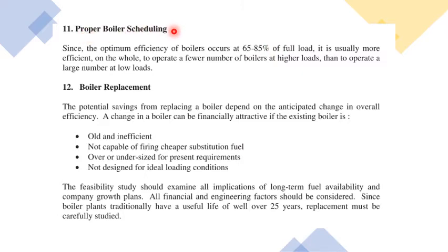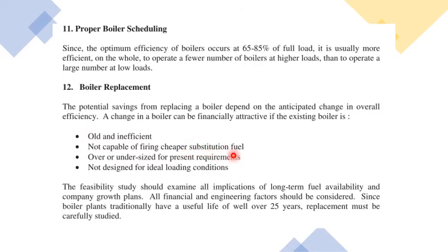The twelfth point is boiler replacement. If a boiler is old and inefficient, not capable of firing cheaper substitute fuels, oversized or undersized, or not designed for ideal loading conditions, it may need to be replaced. Over the years, plant loads change and older boilers may not handle new fuel types. Replacing an old boiler can improve efficiency and lead to better energy conservation.